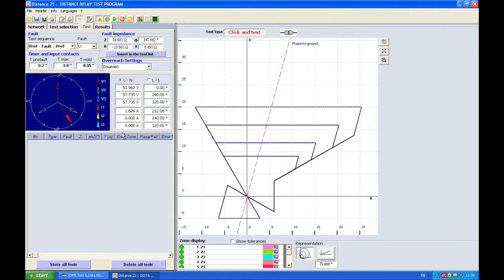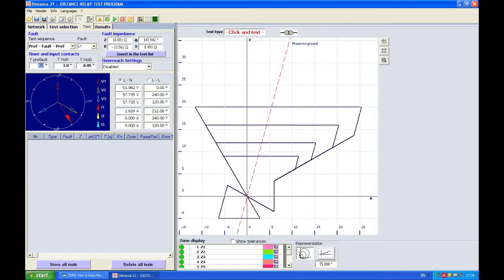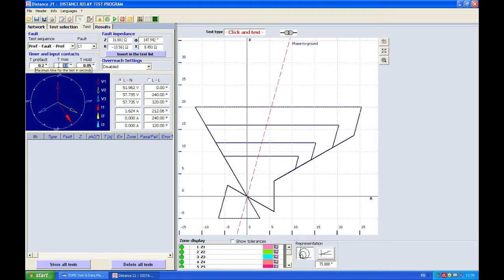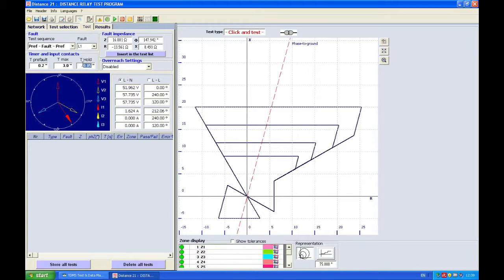Another thing you can do is you can control the prefault time so for 0.2 seconds when I press click I will be generating nominal prefault values. My maximum generation time is three seconds. Be always careful that this time is longer than the longest tripping time otherwise you won't be able to test the highest zone. Hold is for how long will the DRTS be holding the current after it receives the trip command.